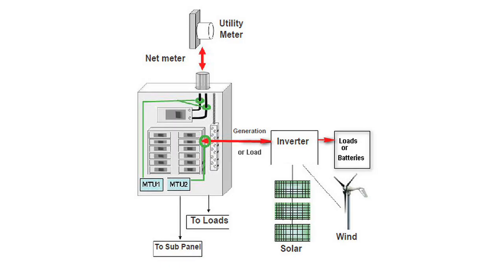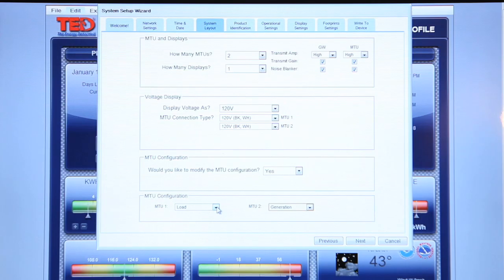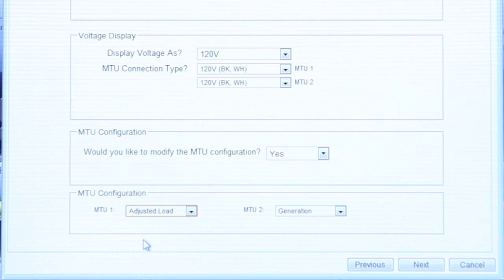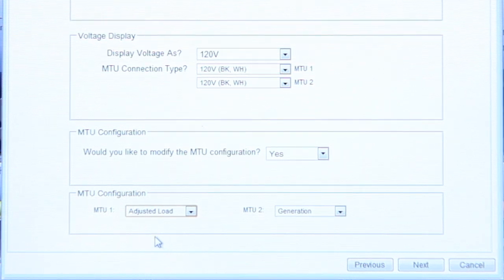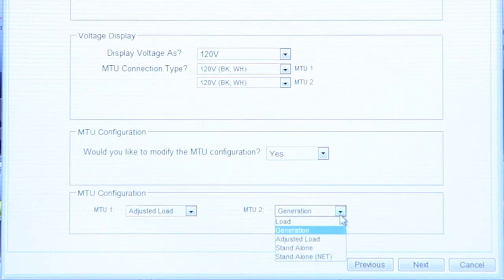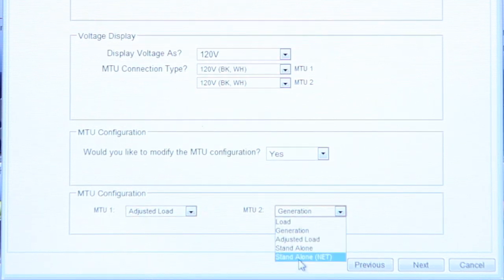The third configuration is for a generation system where the generation source feeds a battery backup or downstream load. In this particular setup, there could be loads downstream from the CTs. Set MTU 1 to adjusted load — this will show MTU 1 as a measure of value into and out of the grid. Set MTU 2 as stand-alone net to capture positive and negative values.